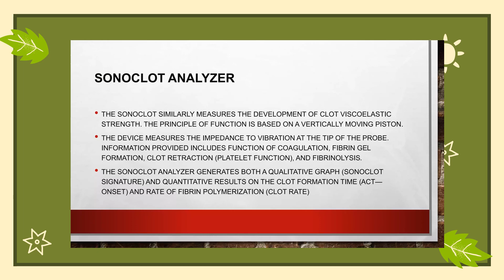Sonoclot analyzer. The Sonoclot similarly measures the development of clot viscoelastic strength. The principle of function is based on a vertically moving piston. The device measures the impedance to vibration at the tip of the probe. Information provided includes function of coagulation, fibrin gel formation, clot retraction, and fibrinolysis. The Sonoclot analyzer generates both a qualitative graph and quantitative results on the clot formation time and the rate of fibrin polymerization.